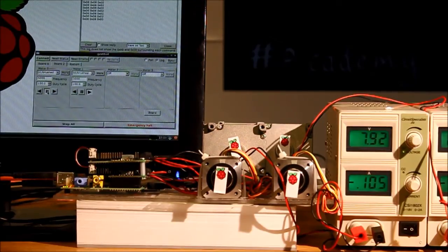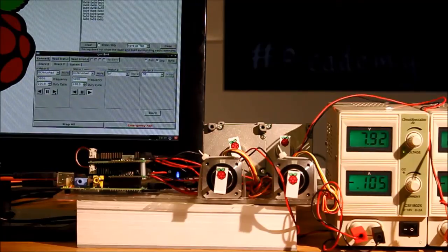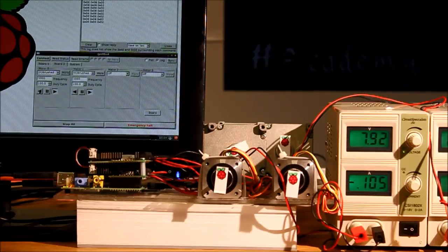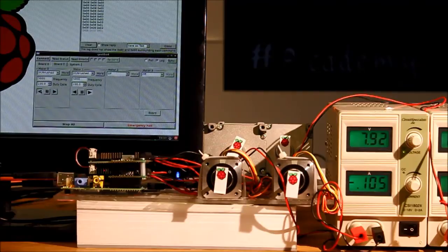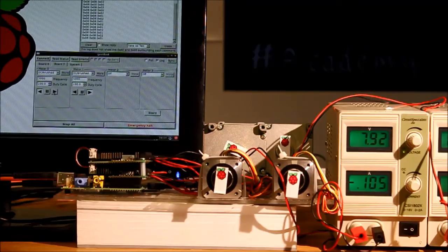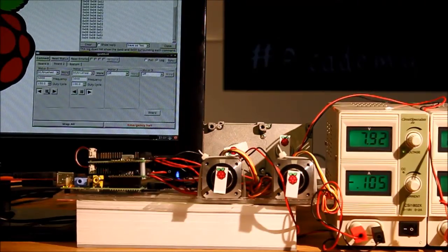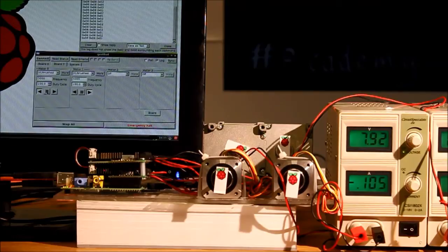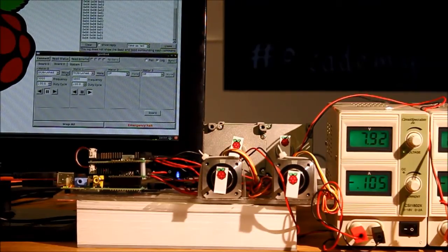However, there is a situation in which you can force this for a longer period of time. If I switch from full forward to full reverse, the short circuit is present for a longer time and you can hear the circuit responding. That little squeal you hear is the short circuit oscillating for a longer period of time and giving enough energy for the motor to start. So at the moment the microcontroller is told to ignore the error.